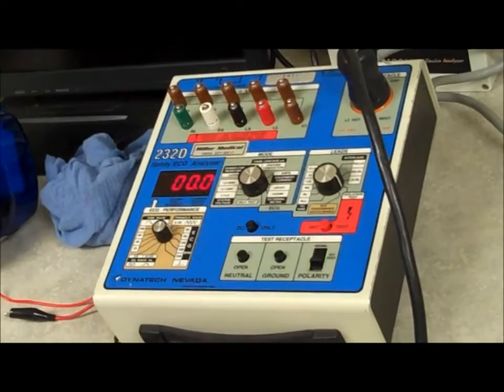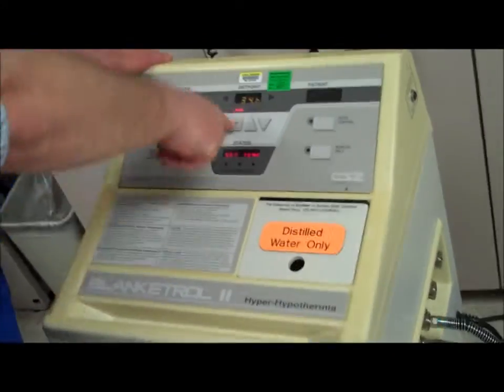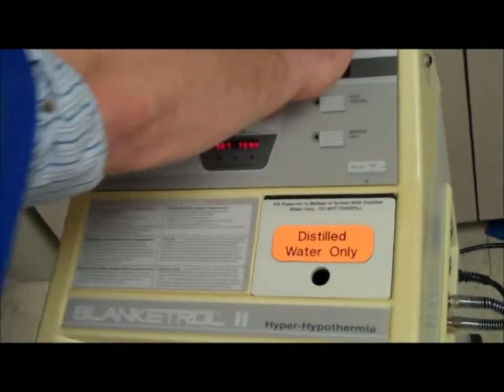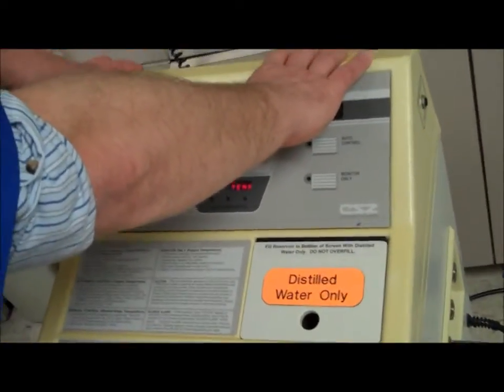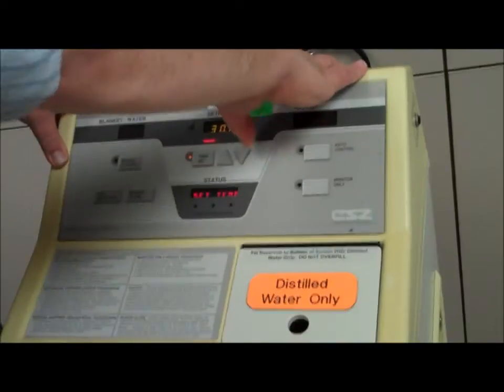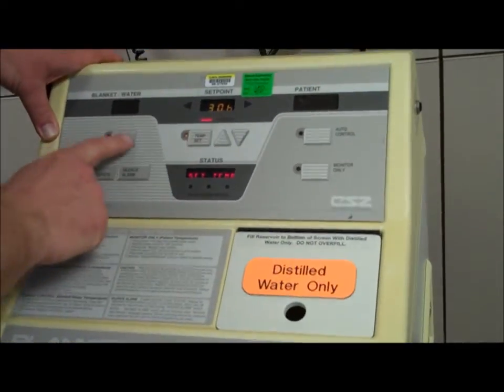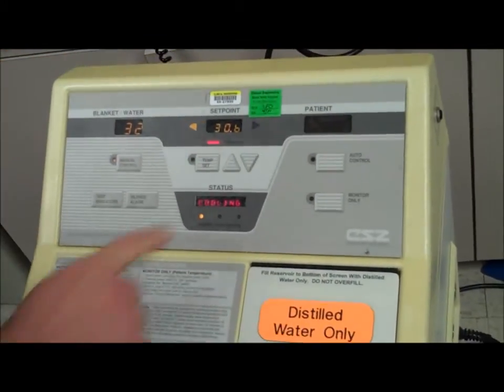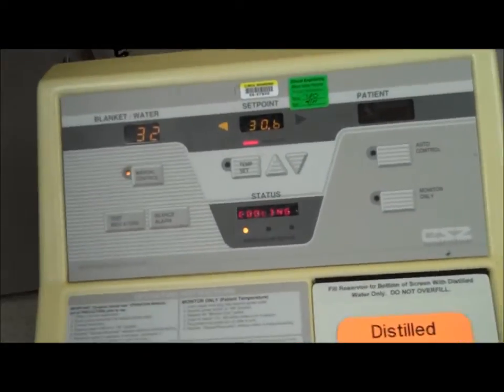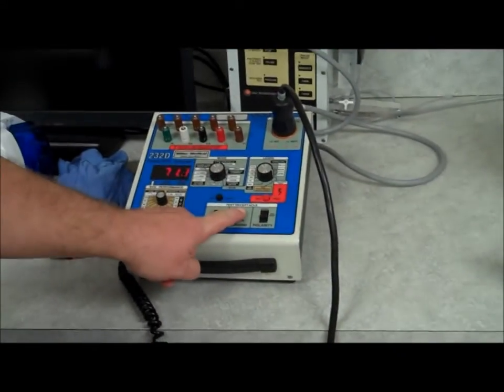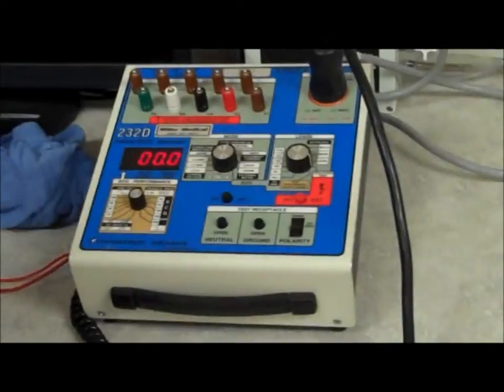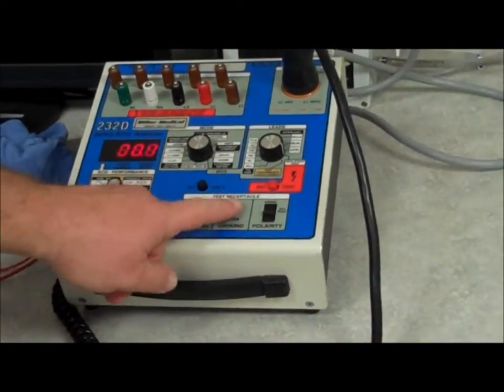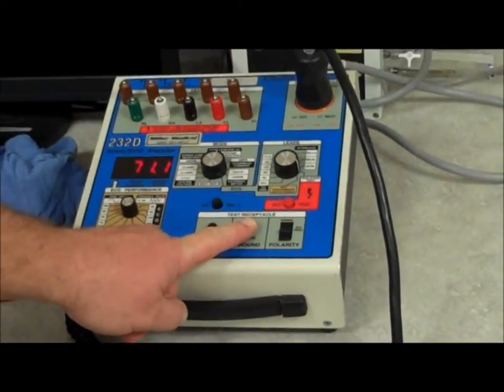Now we're going to check leakage current versus the cooling cycle. Set our temp, drive to a cooling temperature. Manual control comes on. We should see the cooling, and that's within our range on the leakage current. That was around 71.